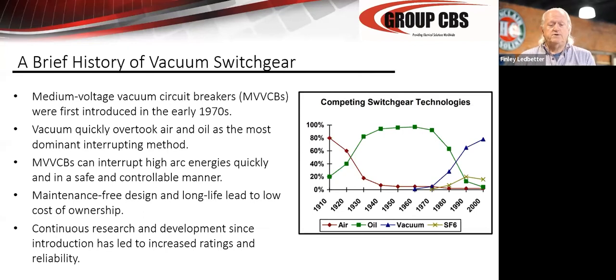Medium voltage vacuum interrupters can interrupt current very quickly at the next current zero crossing. So they're very quick, they're very simple, they're very easy to use. They use very small, very lightweight mechanisms, so they're easy to maintain, and they quickly became, you know, the chosen type of interrupting for the American medium voltage market. They're very long life and low cost of ownership. Now, there are some downfalls to the medium voltage vacuum breaker, one of which is the breaker does typically age out. It can be maintained and kept in service, but they do age out.